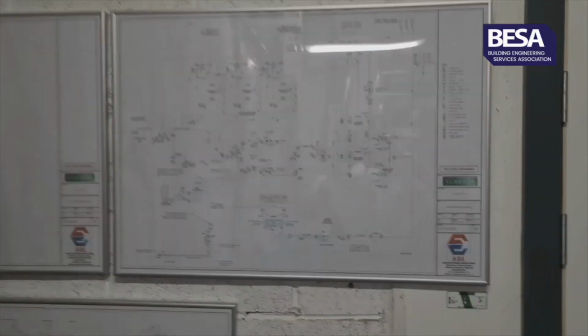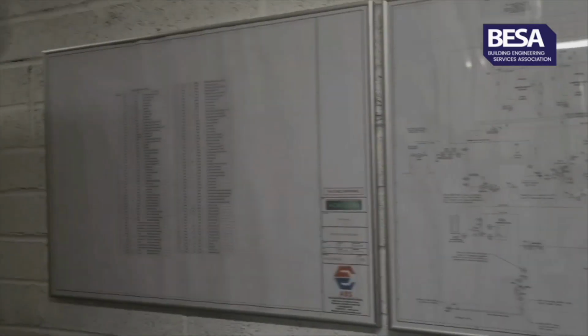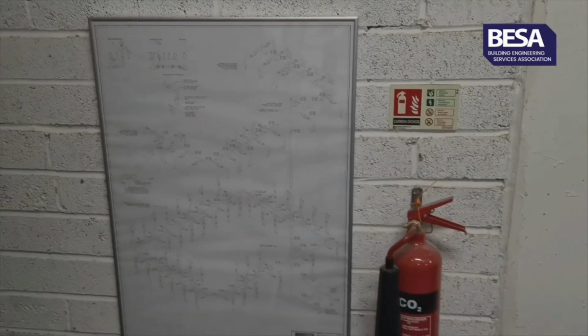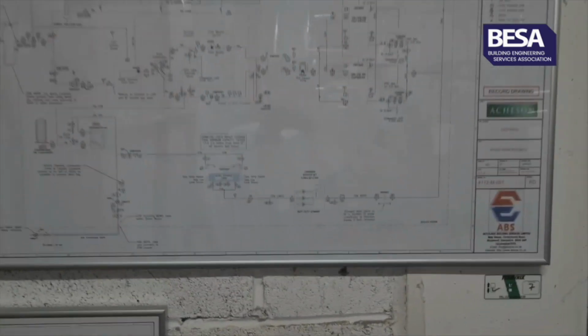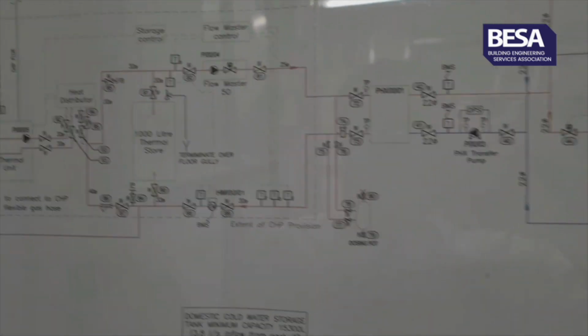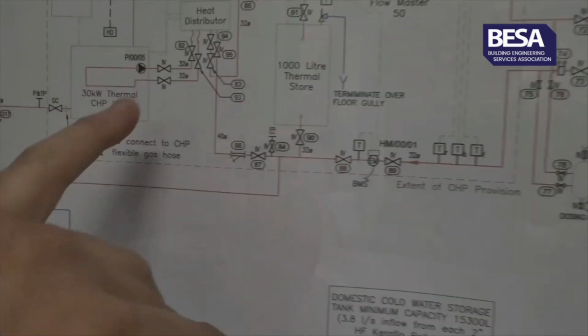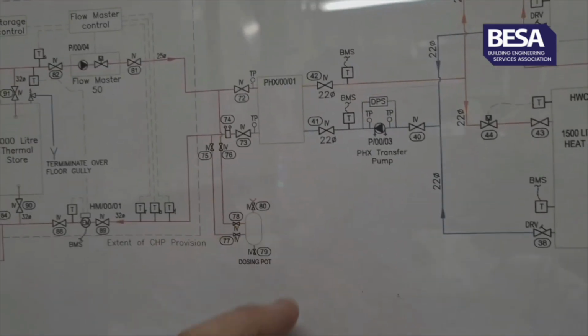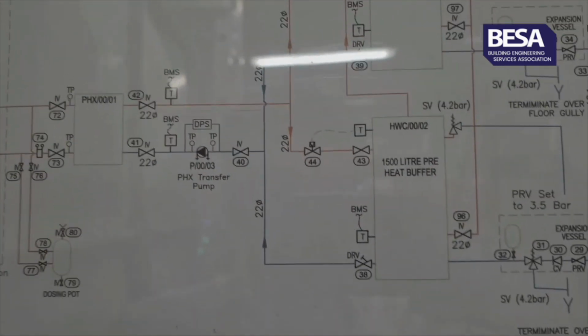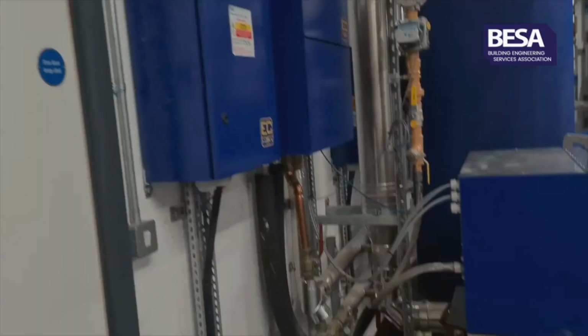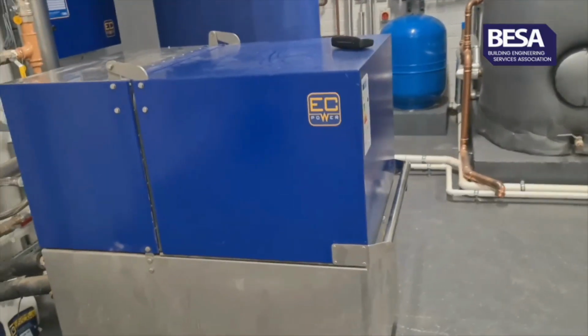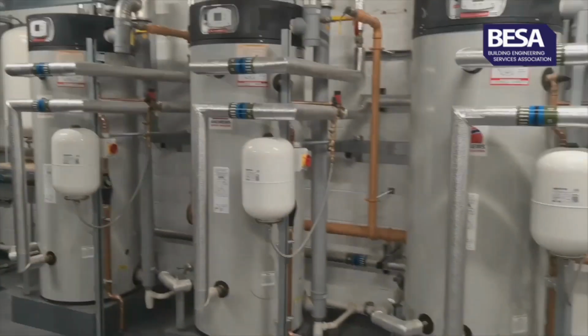So over here we have the schematics, about the best place we could find to stick them, to be perfectly honest, but they work, they're fine. There's a valve chart here, which correlates to the numbers in the plant room, and then correlates to the drawings. So you've got your CHP here into a thermal store, which is then divided by a plate heat exchanger, and then you have a transfer pump which basically takes the water back into the buffer vessels. So the whole theory is the CHP does the work, and then if there's more hot water demand required, then the gas-fired water heaters kick in.